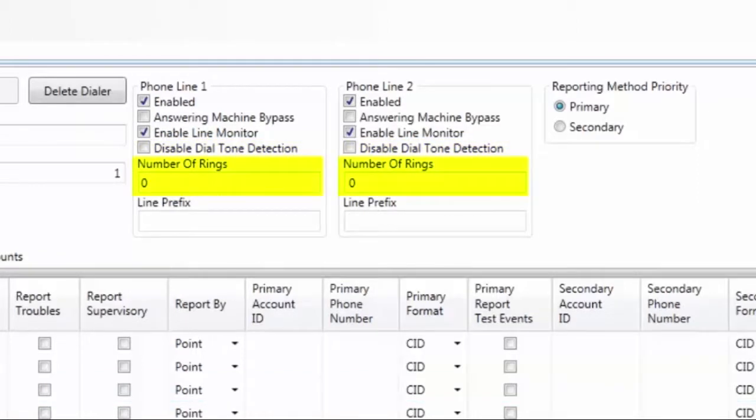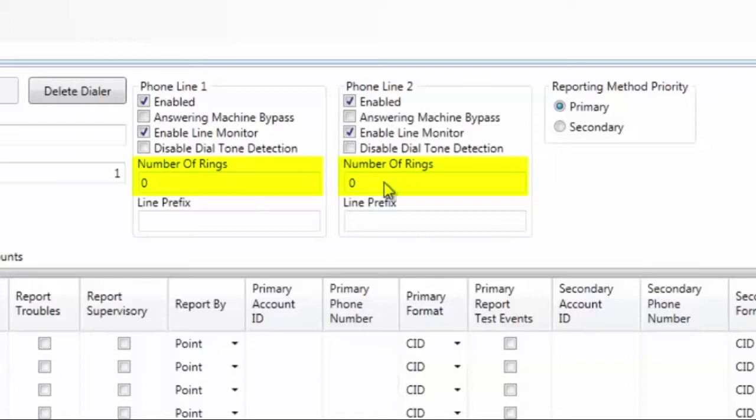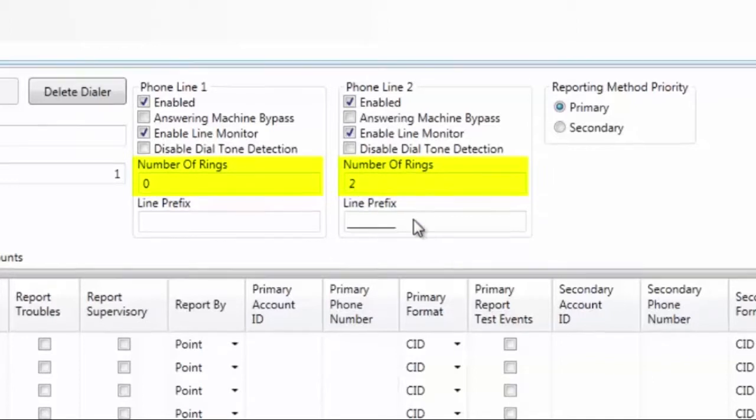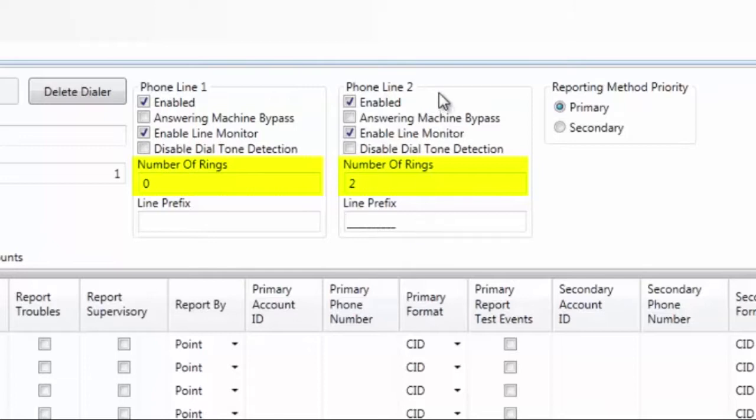Next is the number of rings. If you plan on accessing the Fire Alarm Control Panel remotely via a modem, the number of rings refers to when the UD1000 will answer that call. Whoever provides the phone lines for the UD1000 will provide phone numbers that can be used to call into the Fire Alarm Control Panel. The default here is 0. If you want the UD1000 to answer the call, you will need to change this to something other than 0. For example, if I change this to 2, that means that the UD1000 will answer the call after 2 rings when calling into phone line 2.